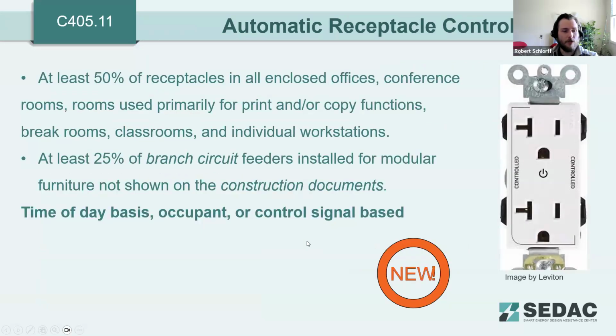Automatic receptacle control. This is another new and potentially big change in the 2021 code: automatically controlled receptacles are now required within certain circumstances. The automatic receptacle controls are required in at least 50% of receptacles in all enclosed offices, conference rooms, rooms used primarily for print and/or copy functions, break rooms, classrooms, and individual workstations.